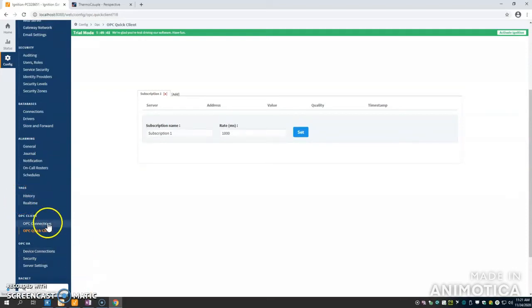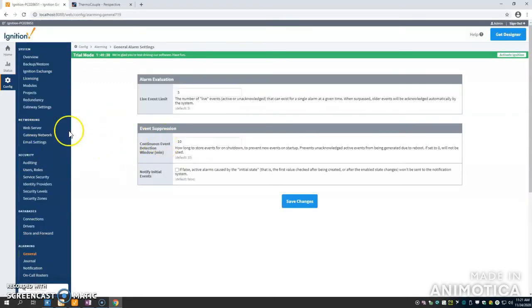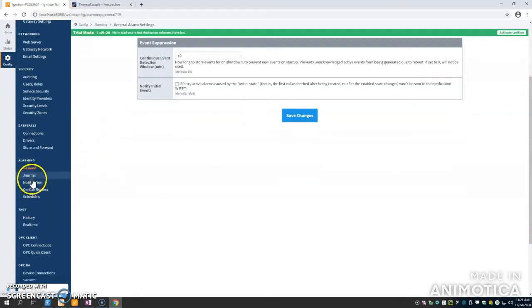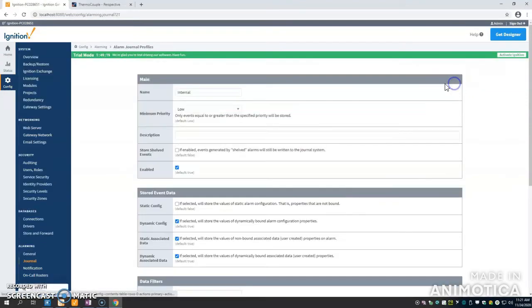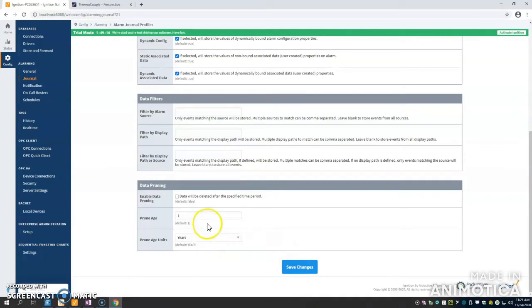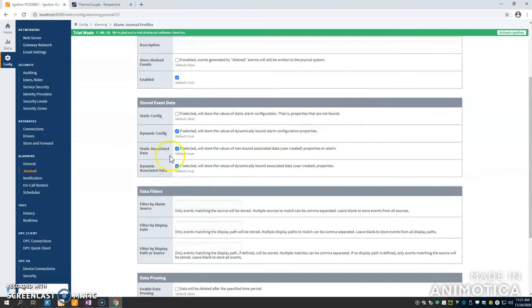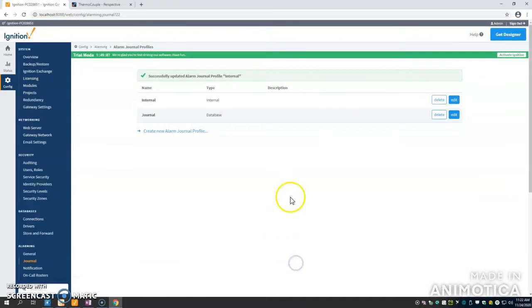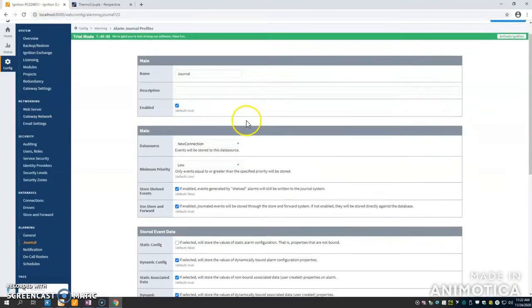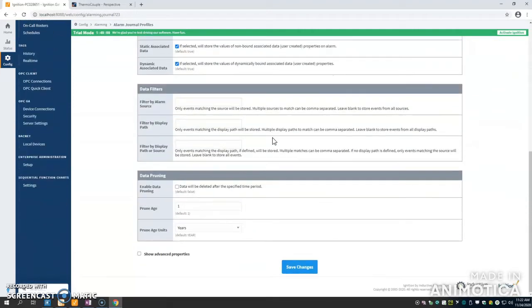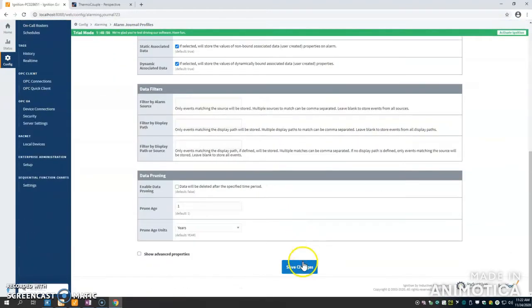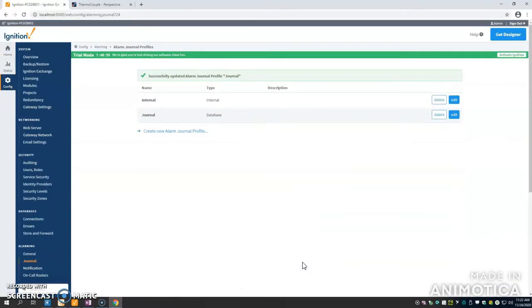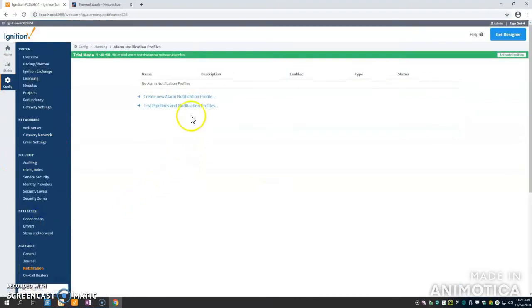There's so many settings in here that I'm not going to discuss all of them, but one that is important would be alarming, obviously. So you configure alarms, the actual alarms in designer, like I said, like set points and such, but in the gateway, you select the pipelines, and if you want mail, email, or calling involved with it, you can configure that all from here. So this is the pruning I was talking about. If the alarms are too old, they will be omitted and deleted, which will be important. So you don't have your equipment bogged down as much with old data if you don't need it. That does have downsides, though, if you want to reference way back. But all of them are fairly easy to configure an external database, so you can support internal, external. You just have to connect it. You have to make database connection if you need that.